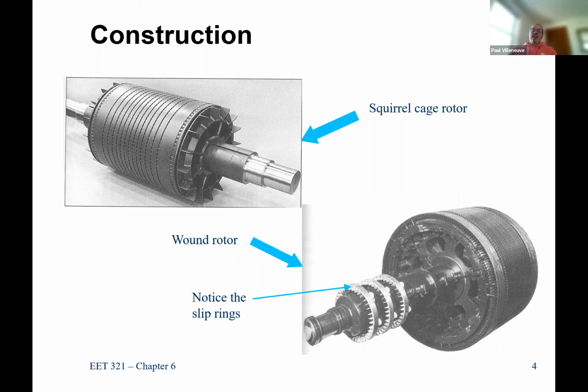And remember what we said, the synchronous machine only will put out 60 hertz when it runs at, let's say, 1800 RPM. An induction machine works perfectly fine at 1800 RPM, and it can run at lower speeds than that if it's a motor. No problem whatsoever. So that variable speed capability is why they use that. They still will output 60 hertz, but they don't have to spin at synchronous speed. So that's why wind turbines have been using doubly fed induction generators. And we'll talk about why it works so well when we get into more details of the construction.